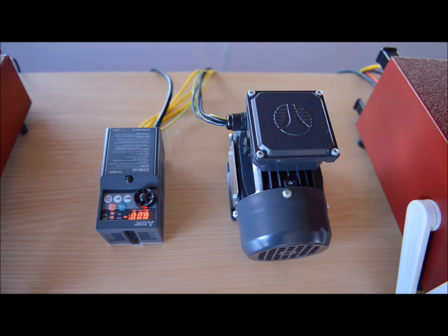and we'll now look at how to set up the analyzer for this device. Now, this device has a variable switching frequency, but today the switching frequency is going to be set to approximately 8 kHz, and that's one of the most important points to remember when you're going to be setting up an analyzer to measure an inverter drive, because the switching frequency is what we want to be filtering out in order to lock onto the frequency.